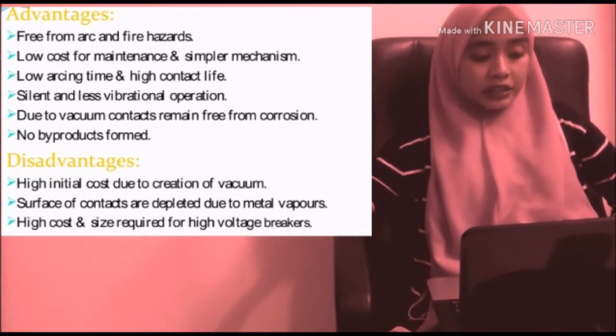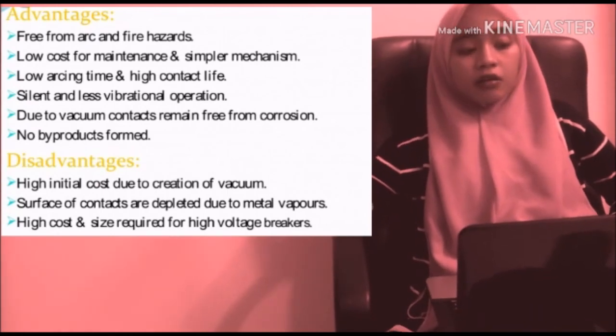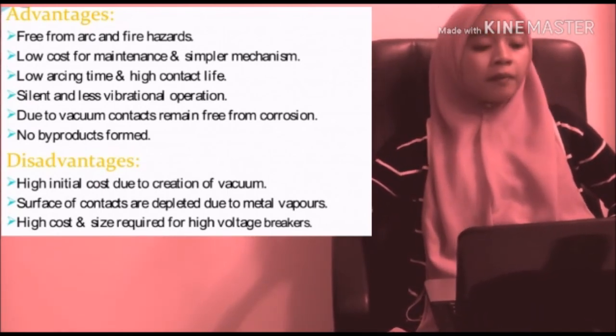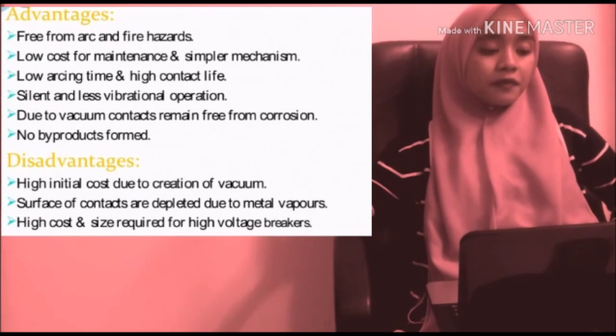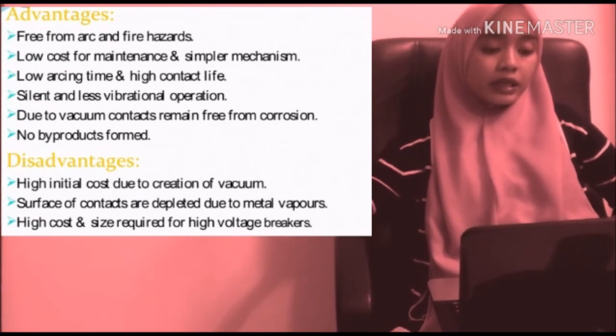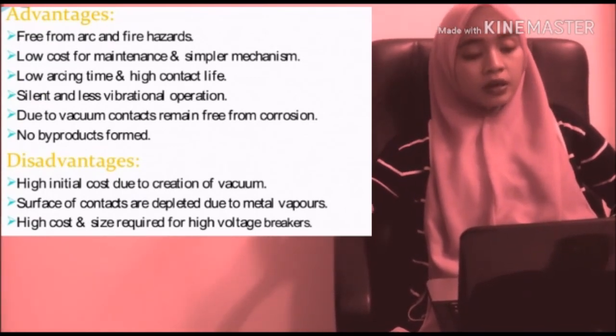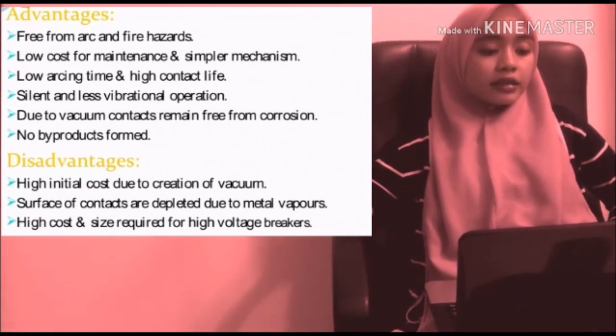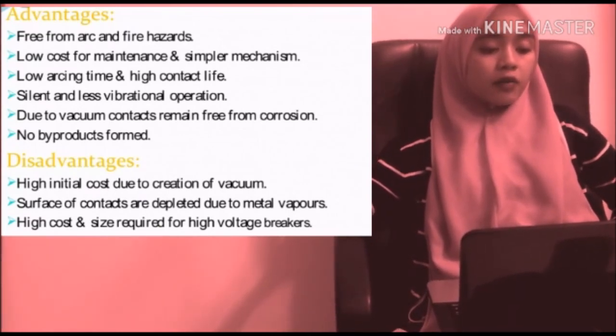Okay, disadvantages: high initial cost due to creation of vacuum. Surface of contacts are depleted due to metal vapor. High cost and size required for high voltage breaker.